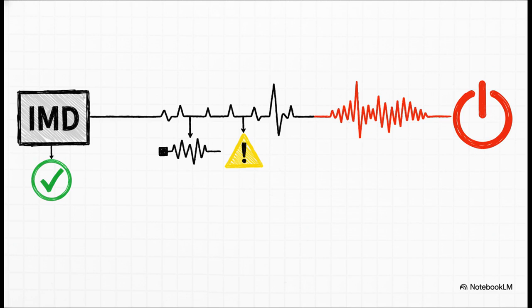But the one you really have to listen for is 50 hertz. That frequency means earth fault. It's a critical failure, and your hardware decoder has to see that 50 hertz signal as an absolute command to shut the whole system down right now.